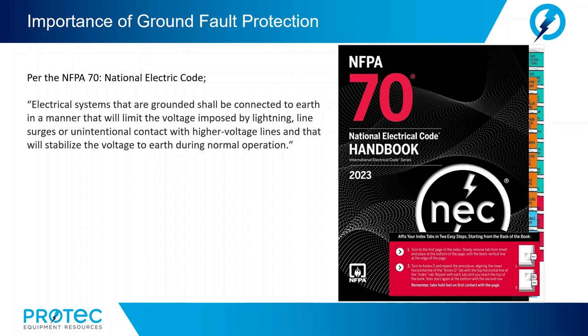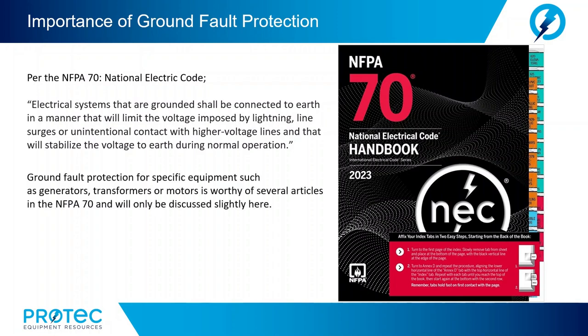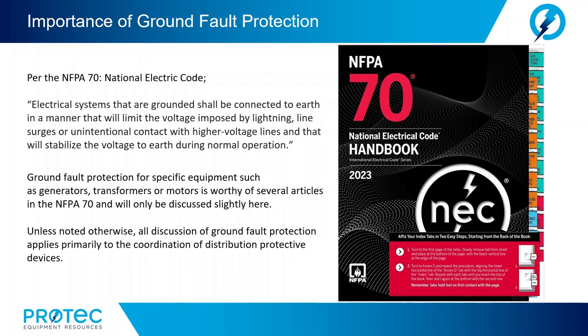Per NFPA 70, the National Electric Code, electrical systems that are grounded shall be connected to Earth in a manner that will limit voltage imposed by lightning, line surges, or unintentional contact with higher voltage lines, and that will stabilize the voltage to Earth during normal operation. Ground fault protection for specific equipment such as generators, transformers, or motors is worthy of several articles in NFPA 70. Unless noted otherwise, all discussions of ground fault protection apply primarily to the coordination of distribution protective devices.